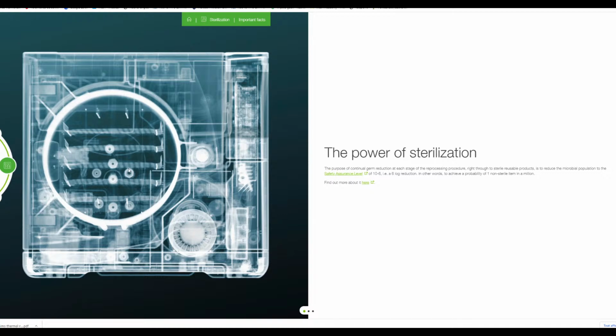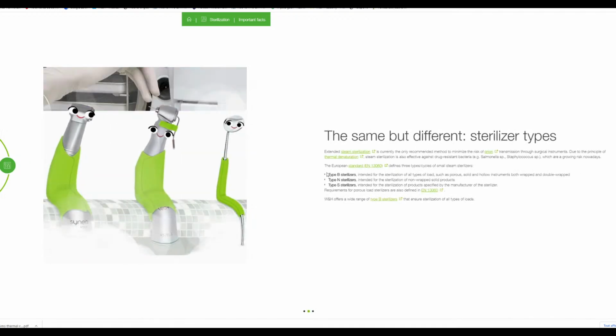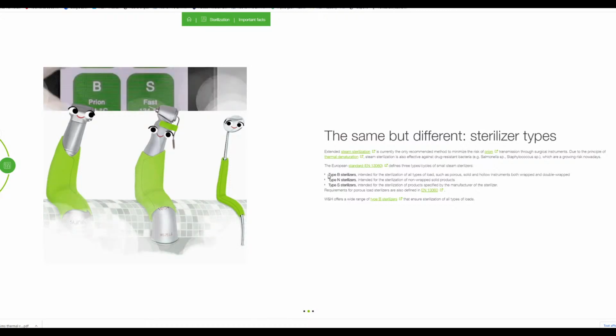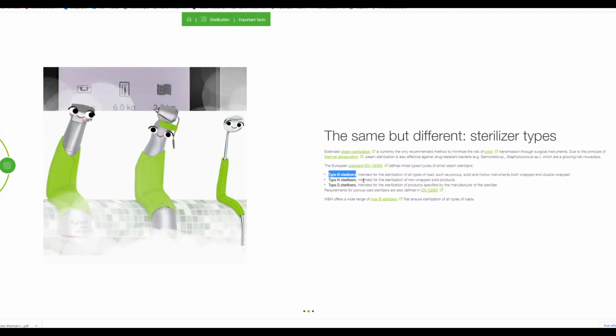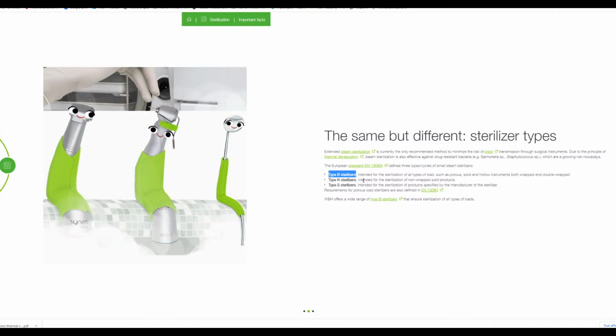I mean, you have to pre-clean, pre-disinfect the instruments. Only cleaned and pre-disinfected instruments can be sterile. This is also the case in big hospitals. They would never process instruments which are not perfectly cleaned, because any residue can lead to non-sterile instruments. Therefore, we have this circle with the details. Here we explain the differences in cycles. A B-type cycle, B comes from big sterilizer. This is our recommendation. Use B-type cycles. Very often the assistant has many buttons on the sterilizer, and he or she will click on any button. But how can we be sure that this selected cycle is compatible and designed for the processed instruments? This is a question you have to ask yourselves all the time.